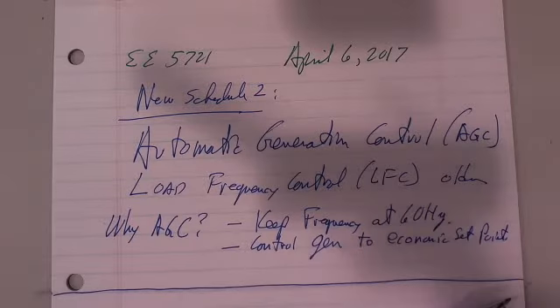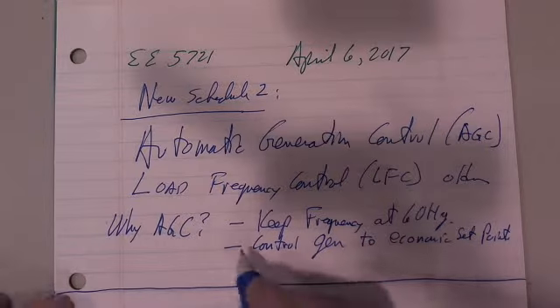In other words, we run economic dispatch, and it says this generator should be putting out exactly this much to be the most economic generator, and the control system that keeps the generator at that point is the AGC. So it's the means of, they don't call up the plant and have the guy dial it in. That won't work. It's done with a feedback control system that comes from measuring the plant output all the way back to the AGC, and then all the way back into what we call the speed governor on the plant.